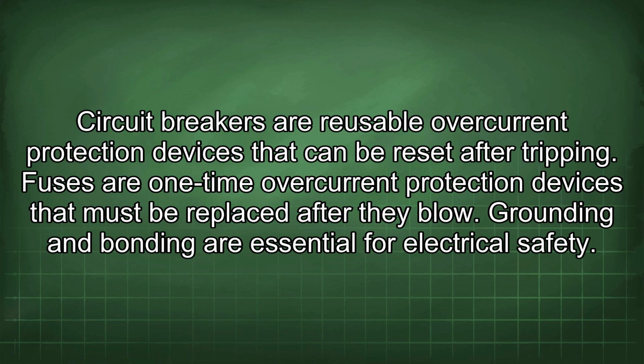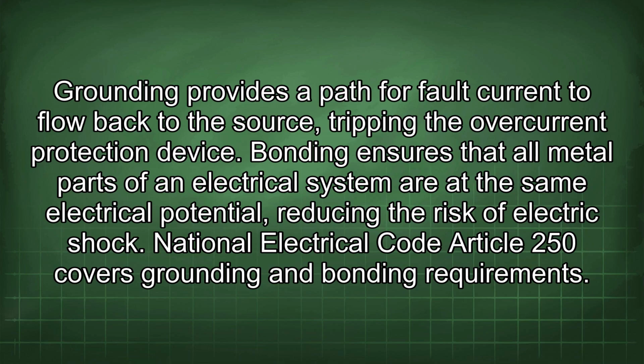Grounding and bonding are essential for electrical safety. Grounding provides a path for fault current to flow back to the source, tripping the overcurrent protection device. Bonding ensures that all metal parts of an electrical system are at the same electrical potential, reducing the risk of electric shock. National Electrical Code Article 250 covers grounding and bonding requirements.